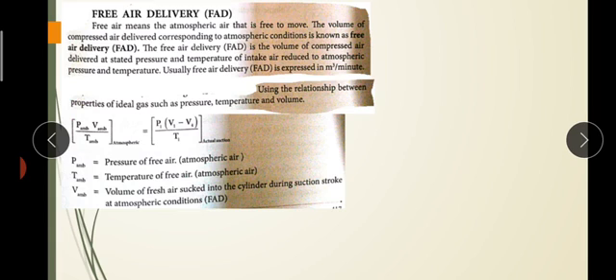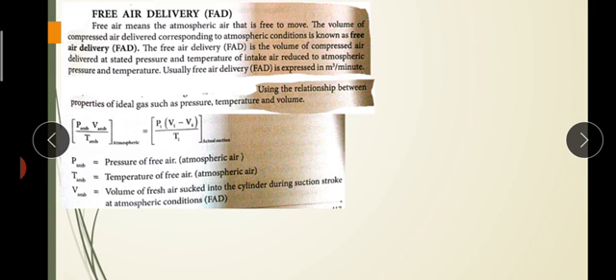The volume of compressed air delivered corresponding to atmospheric conditions is known as Free Air Delivery. The F.A.D. is the volume of compressed air delivered at stated pressure and temperature of intake air, reduced to atmospheric pressure and temperature. This is measured in cubic metres per minute.